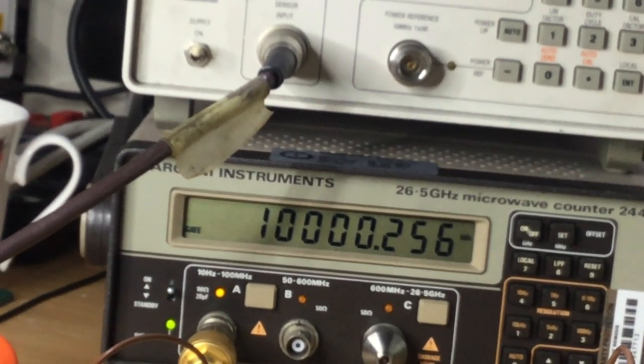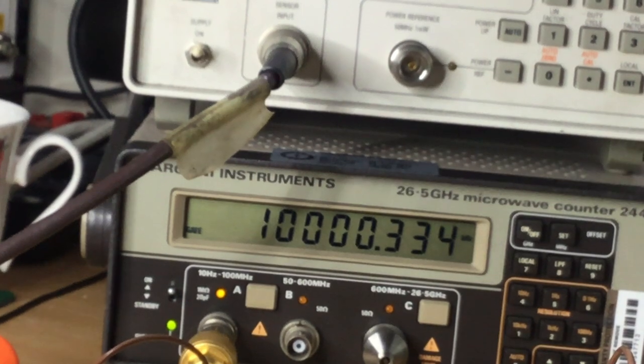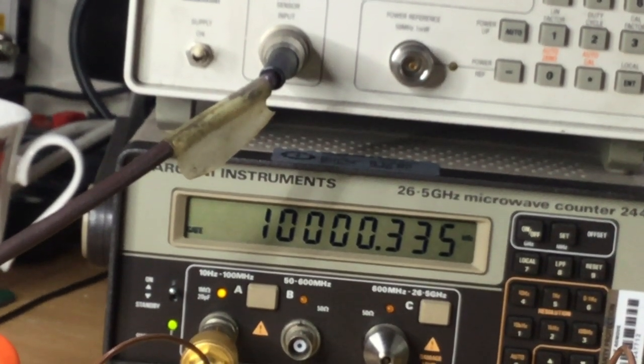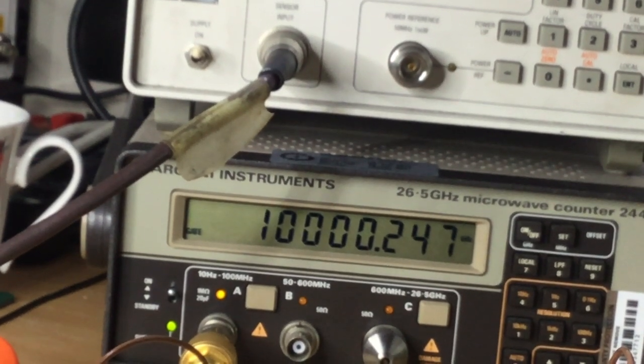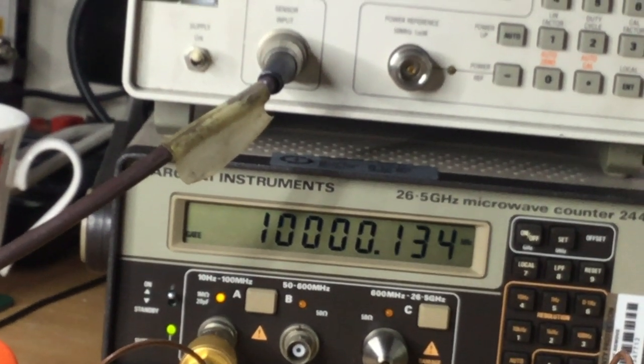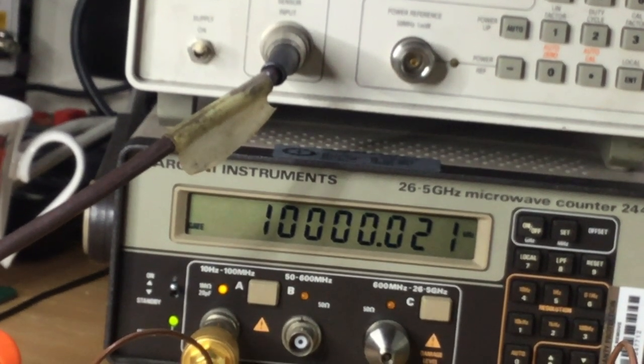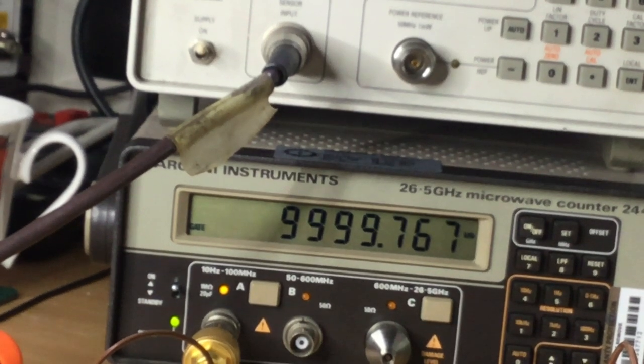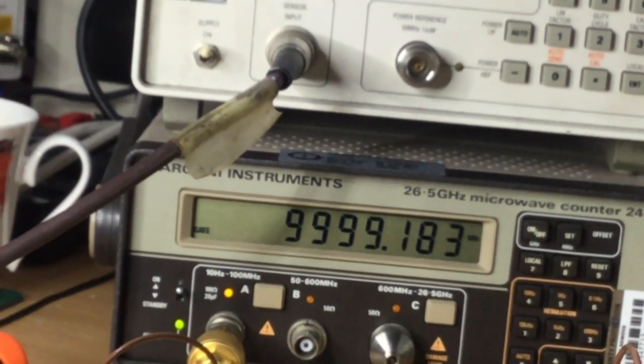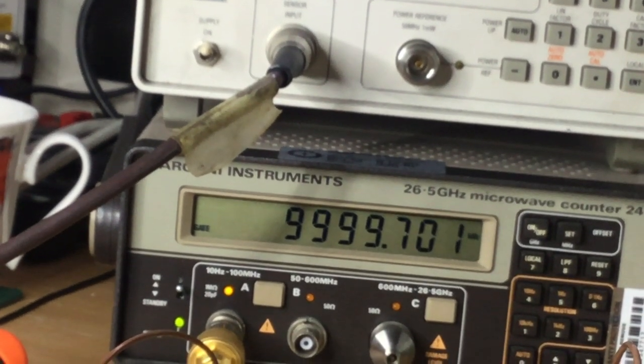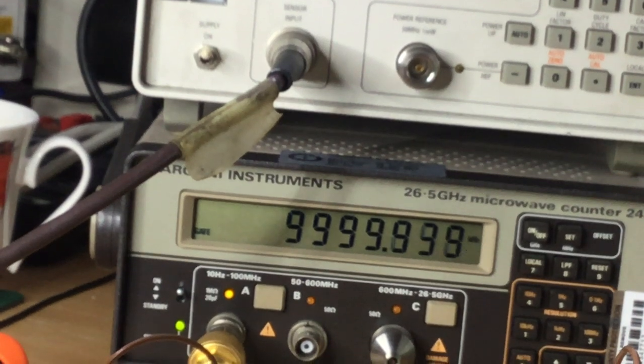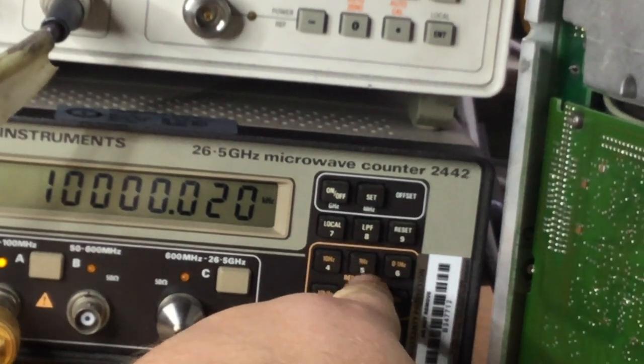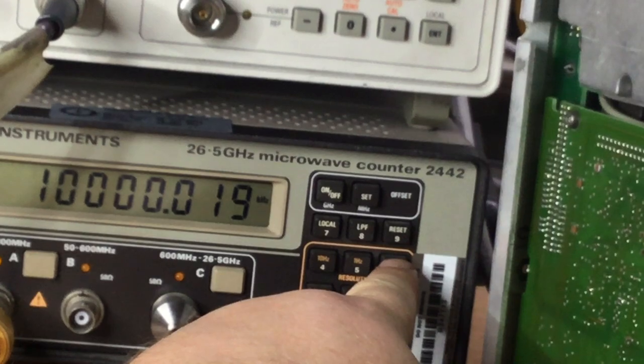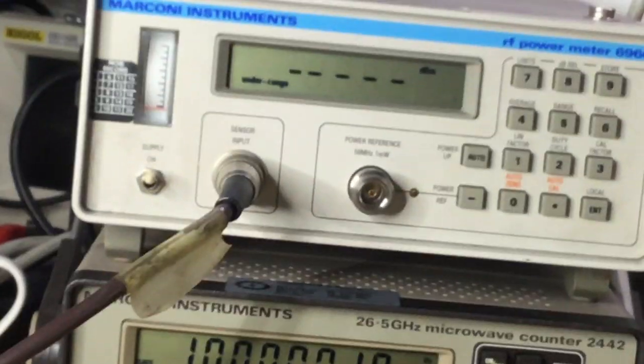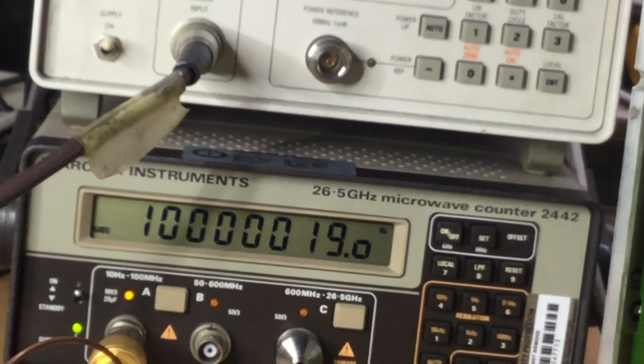Now obviously with it being a reference oscillator, 10 megahertz, the multiplication of the frequency changes here, although they're very small and minute on the 10 megahertz signal, has a major change obviously under normal circumstances on the 300 megahertz calibrator signal. So I'm just winding the DAC value down again, it's at 17 now, 0, so that's 0, and then obviously to fine tune it at 10 megahertz. So what I will do, we'll just select hertz on this frequency counter. Where is it? That's hertz. So let's see whether we can just adjust it down a bit.